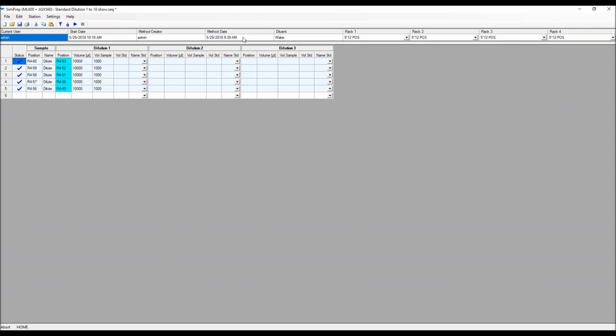Start date and method date. So the start date would be the time that the samples actually run, or when you began your dilution today. Your method date is when that was last altered. And then you have current user and method creator. Within the software, if you want, you can create two different levels of user. You can have an admin, and only the admin has rights to change things like the syringe sizes and a lot of the system settings, whereas the user can still open and run all the methods.